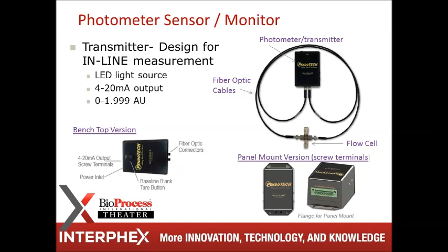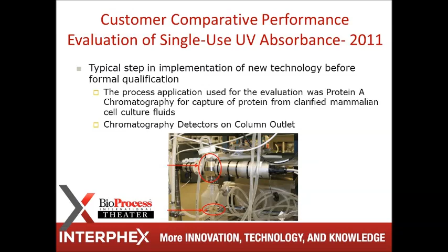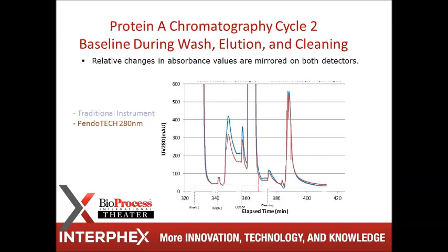The only thing the single-use cell does is give the window and maintain a 1 centimeter path length, and the light source and detector don't touch the fluid. So in this case, you can have a simple photometer that you need to qualify on its own. One of the ways to qualify a photometer would be a comparative performance evaluation. This was early on with one of our customers. They compared the single-use UV to a more traditional instrument in several runs. They recorded the results and found it to be comparable. And so that's another thing that's important when looking at qualifying technology.